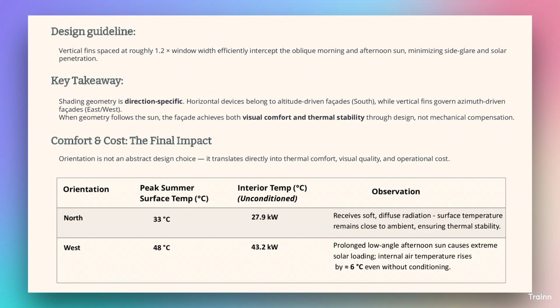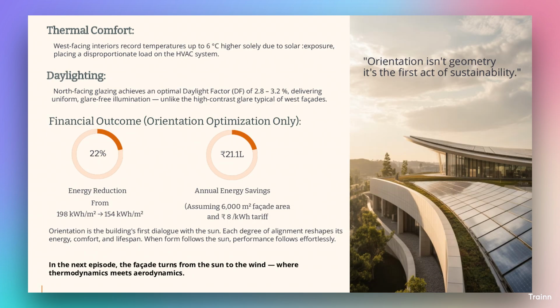Orientation: west. Peak summer surface temp, 48 degrees Celsius. Observation: prolonged low-angle afternoon sun causes extreme solar loading; internal air temperature rises by almost 6 degrees Celsius even without conditioning. Thermal comfort: west-facing interiors record temperatures up to 6 degrees Celsius higher solely due to solar exposure, placing a disproportionate load on the HVAC system.